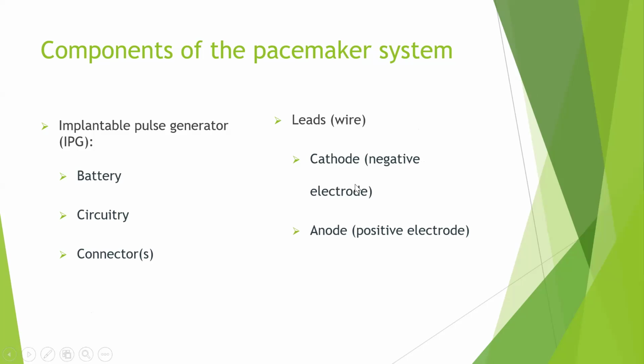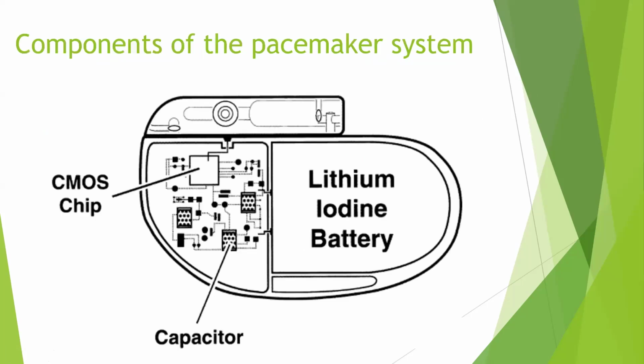And that wire has a cathode and anode. That cathode and anode vary depending on the type of lead. For a unipolar lead, the cathode is going to be the tip of the lead, and the anode is going to be the body tissue. So this is a simple pacemaker, which has three major components as I mentioned.